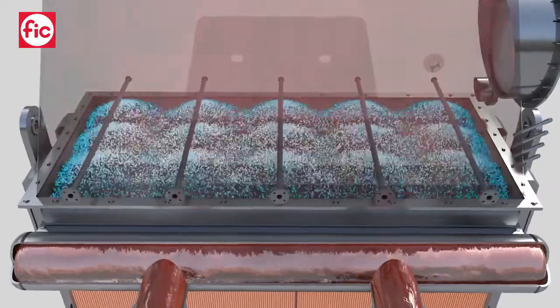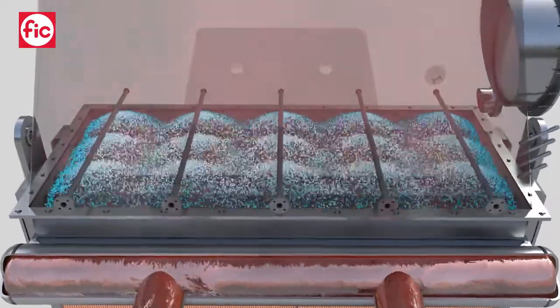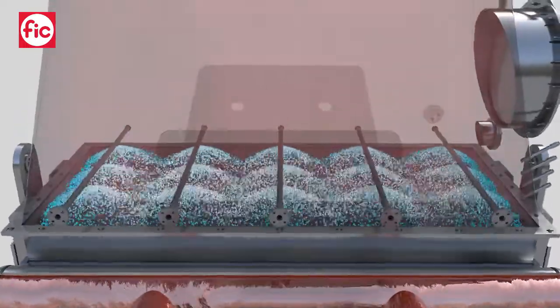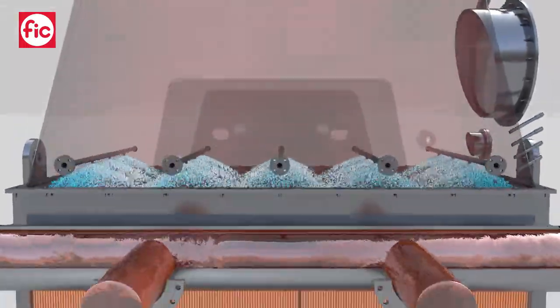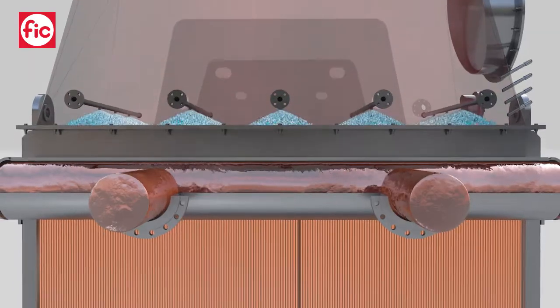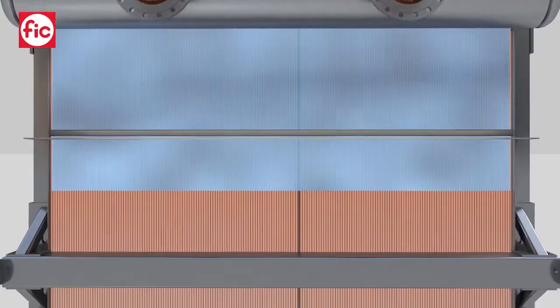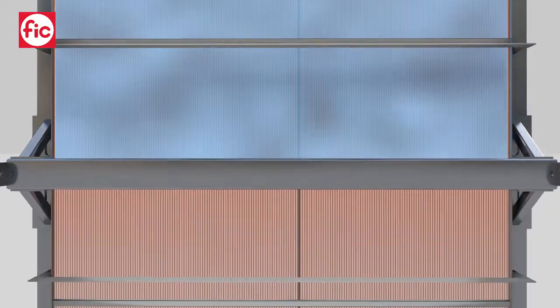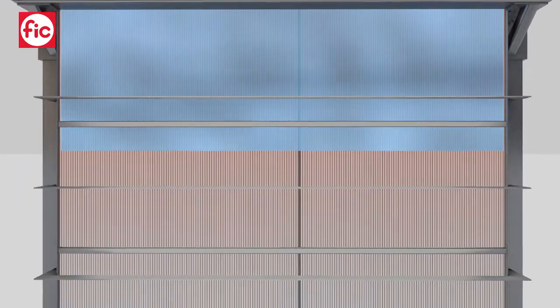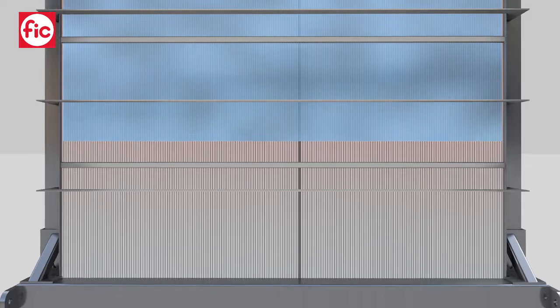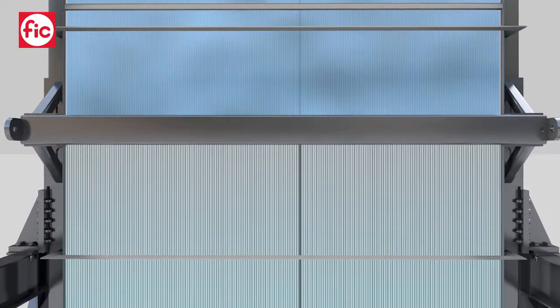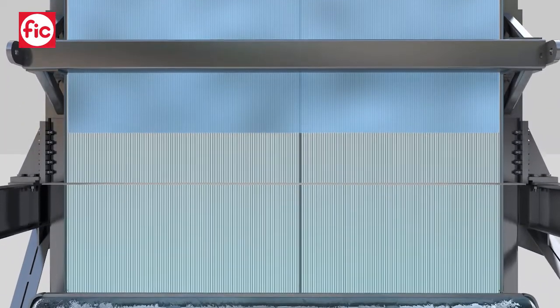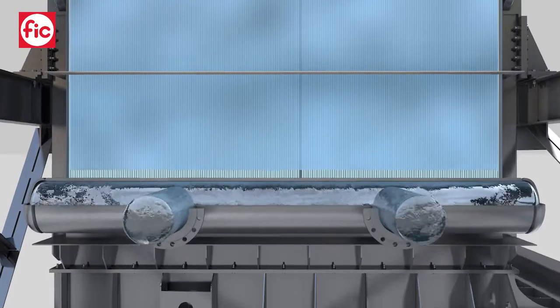The process is designed to always have condensation across all parts of the plate surface. A water film starts immediately at the plate's top edge and increases along the whole plate's length. The gas flowing down is cooled, giving its latent heat of condensation to the water that is warmed up.